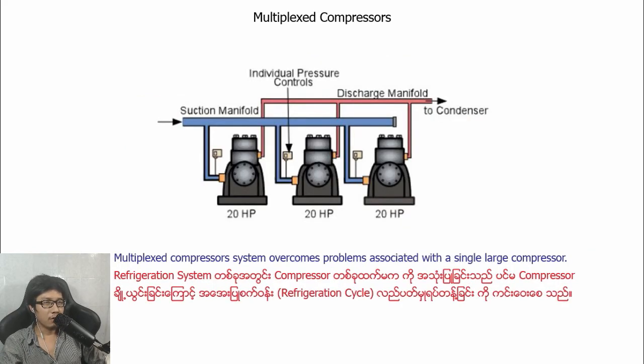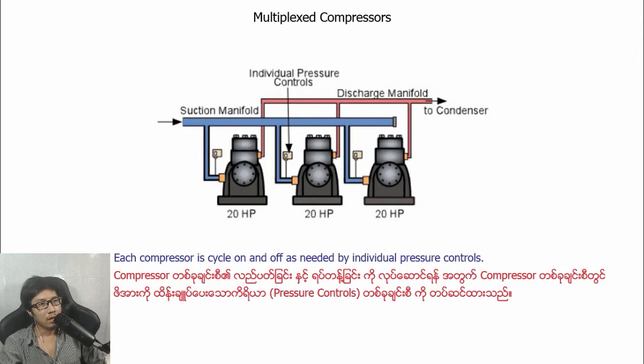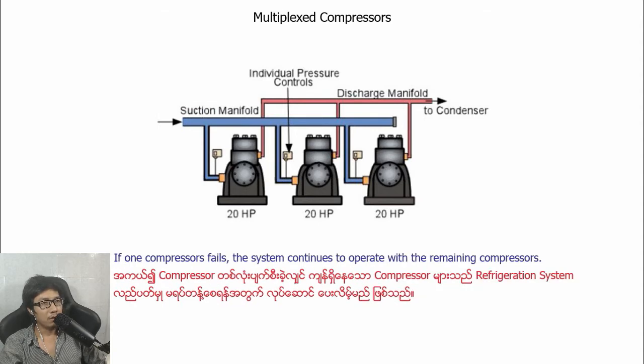Multiplex compressor. Multiplex compressor systems overcome problems associated with a single large compressor. Each compressor is cycled on and off as needed by individual pressure control. If one compressor fails, the system continues to operate with the remaining compressors.